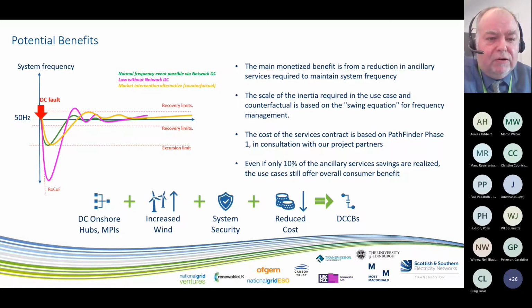And that's what you're seeing in the orange. Now, the point of that intervention is that when you cost that up, the single intervention for a single hub is already into the several billions of pounds. In fact, it could easily get into the tens of billions of pounds, because the level of inertia intervention is more than the minimum inertia limit that the network is currently held to. So that's either via annual contracting or a market mechanism, a significant intervention into the system.